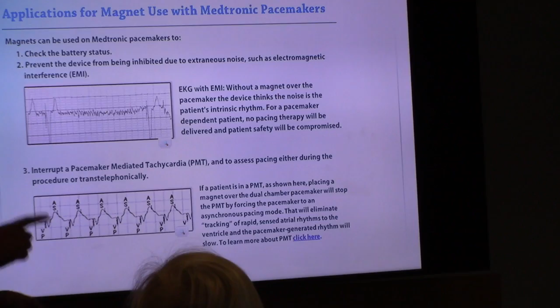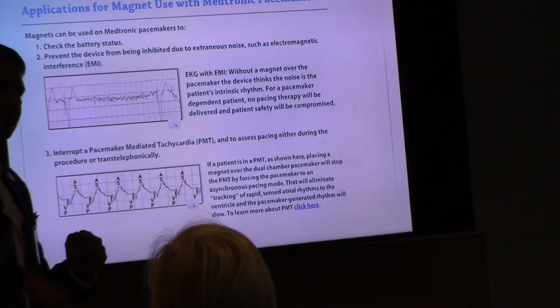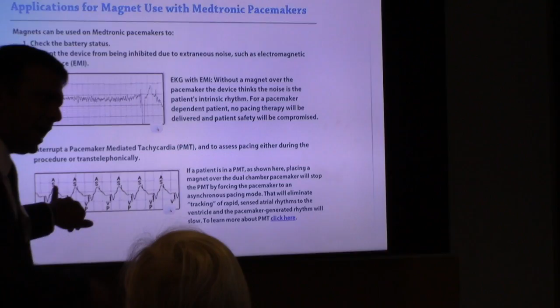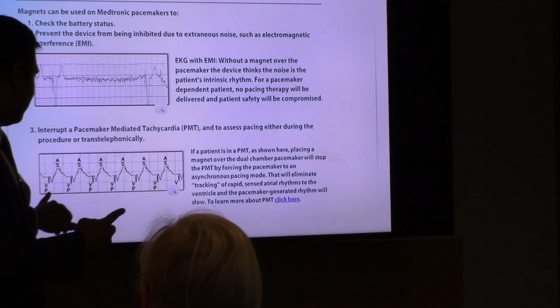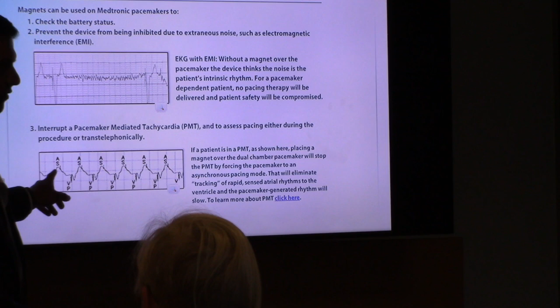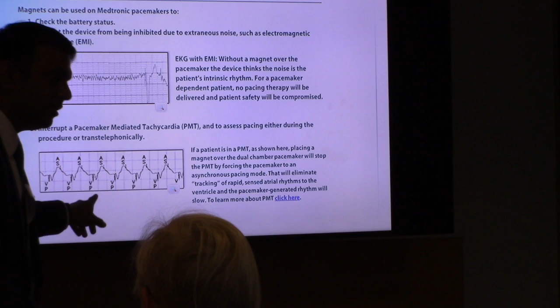Okay, so simply put, there are some patients that would have a retrograde pathway. So let's say you pace their ventricle, right? There would be a sensed atrial event following the ventricular event, because there's a retrograde pathway available in those patients that would basically trigger the atrium after a ventricular pace event. If this atrial event falls in the refractory period of the device, it won't be tracked. However, if it falls into the sense period where the device can sense that event, it will just start pacing, tracking that event. So now the patient is in tachycardia because they are following their retrograde P waves.